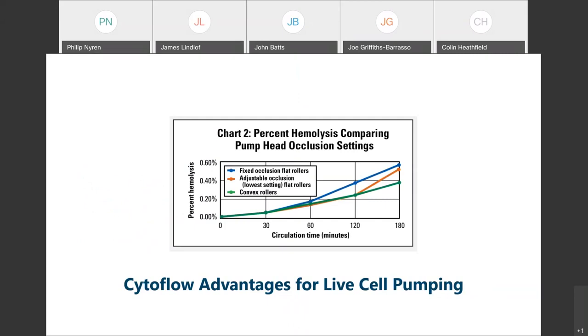So the next subject or product area I want to touch on is the MASTERFLEX LS and IP Cytoflow pumps, which again you saw depicted in that earlier slide. The MASTERFLEX Cytoflow pumps are optimized to pump live cells, large molecules, and any other shear sensitive fluids, and fluid components or suspensions that are prone or could be prone to damage or alteration by the mechanics of pumping. That said, peristaltic pumps are inherently low shear. They are inherently capable of handling large molecules, but the LS and Cytoflow pumps have some design modifications that really optimize that level of functionality.